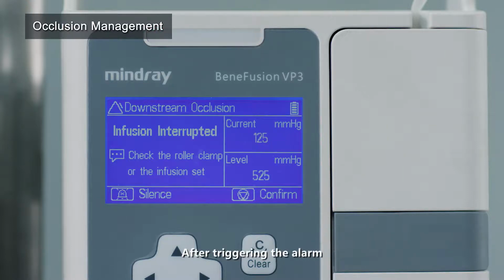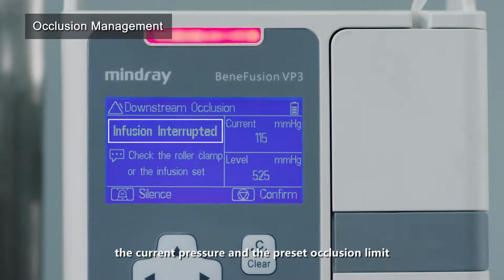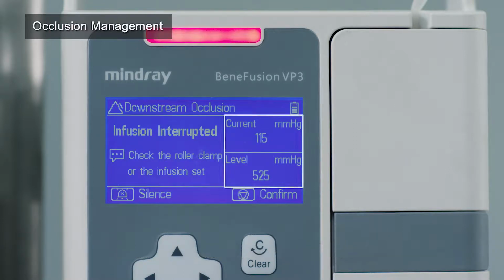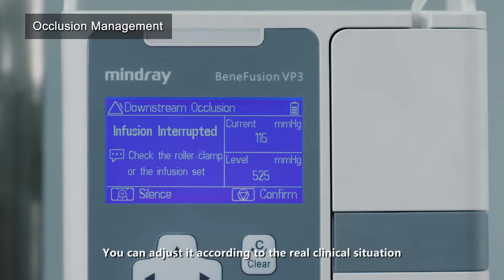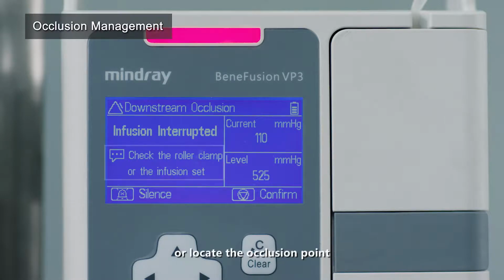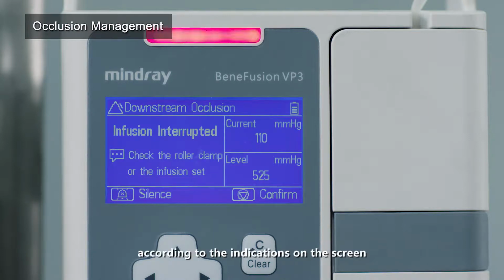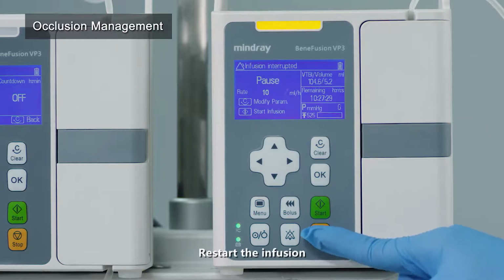After triggering the alarm, the infusion will be interrupted. The current pressure and the preset occlusion limit will show on the screen. You can adjust it according to the real clinical situation by entering into the main menu, or locate the occlusion point and then manage the risk according to the indications on the screen. Restart the infusion.